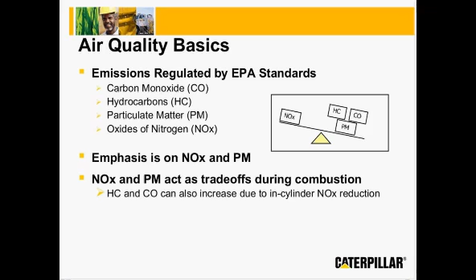So what are some of the things that we as diesel engine manufacturers and generator set manufacturers are doing to reduce emissions? Well, really, emissions reduction technologies can be divided into 2 broad categories. The first category is engine technologies. These are things that we are doing on the engine pre-exhaust to basically reduce the emissions. The first one is working with the combustion control, which consists of increasing fuel pressures to decrease the formation of PM, or the particulate matter. We also are introducing NOx reduction systems, which basically allow us to recirculate a portion of the cooled exhaust gas, which allows us to lower combustion temperatures and decrease NOx production.